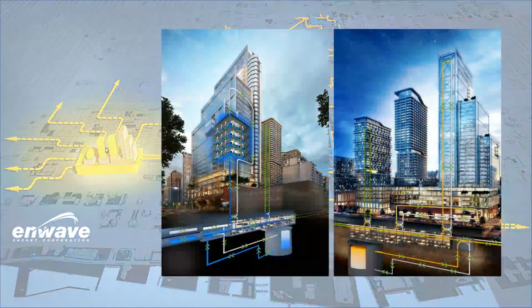We're actually drilling that hole, putting in a thermal storage system that would store heat during, let's say, the winter, when there's low electricity costs and not a lot of heating requirements. During the evening, when there's not a lot of heat needed but we're still generating it, we can store it temporarily in a storage tank. During the summer, we can do the same with a tank for cooling, storing the lack of energy in there.